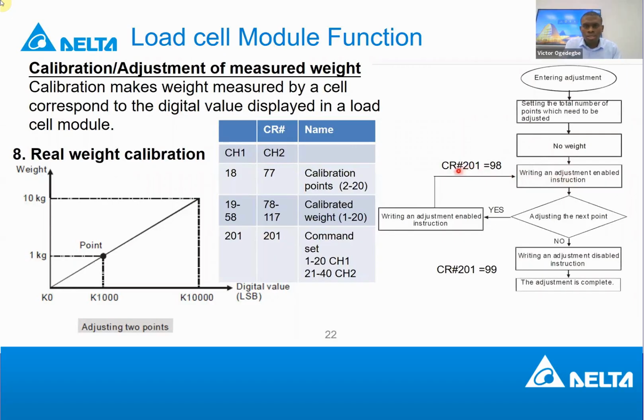To calibrate, in the command set register, you write 98. 98 means write adjustment. It means, as I showed before, activate calibration. Have you done that? Yes. So you have done point 1. Do you want to do point 2? No. Then you write 99, disable calibration. It means you have done 2 points. But do you want to do more points because you want your measurements to be so precise, and your digital value to be as accurate as possible? Yes. Then go back to this stage.